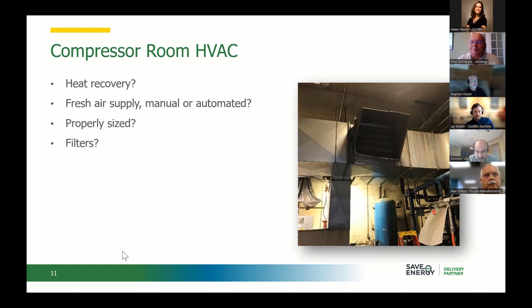Well, an example in this particular photograph is that they have heat recovery into the building for the wintertime from the compressor, but they have no fresh air supply into the room, so the room is always under negative pressure. The temperature on the compressors rises. And they don't close the louvers during the summertime. So the compressors have always been shut down on high temp. And as soon as we opened up one of the man doors, you could see the temperature on the compressor start to drop. So there were duct work issues at this particular customer. As big and as tough as these machines are, they still like to be treated properly.